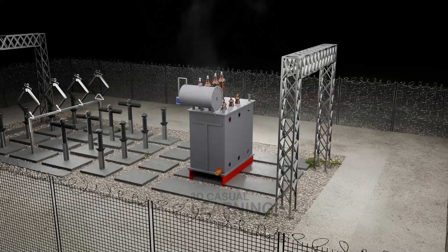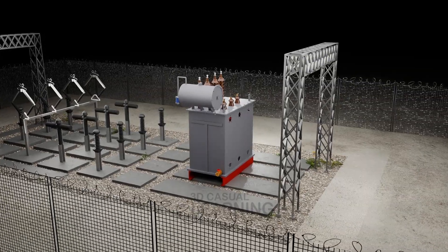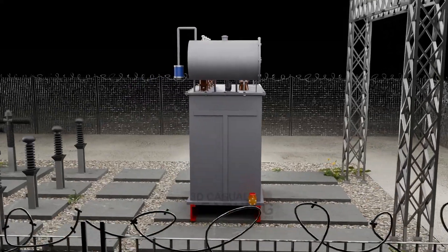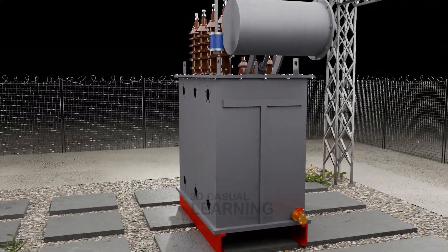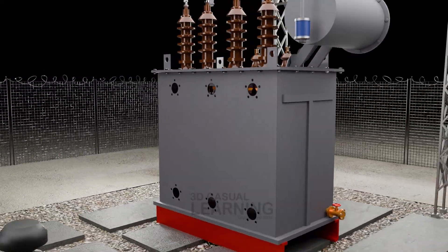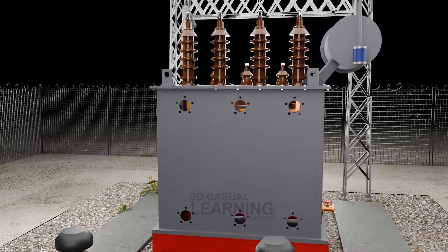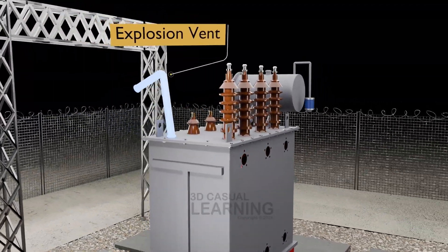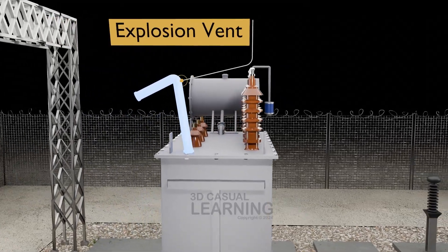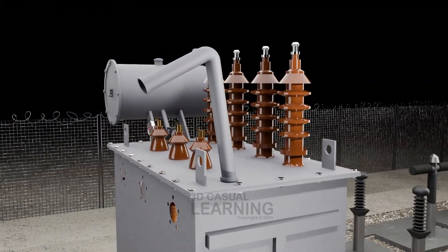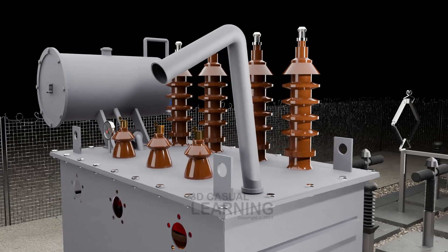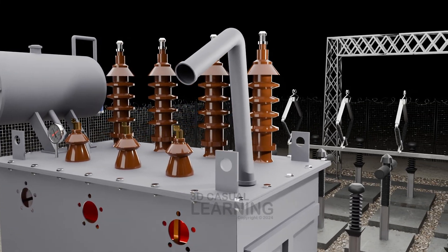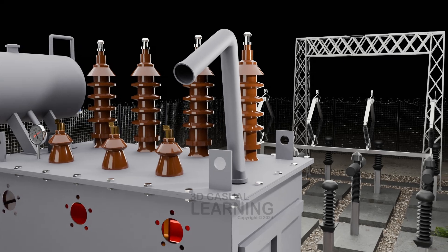To prevent such explosions, explosion vents are installed on the transformer tank. These vents are designed to safely release excess pressure by opening when the internal pressure reaches a predetermined level. When the internal pressure exceeds the set threshold, the explosion vent bursts open, allowing the gases to escape rapidly to the surrounding environment, preventing the pressure from building up further and reducing the risk of a catastrophic failure.